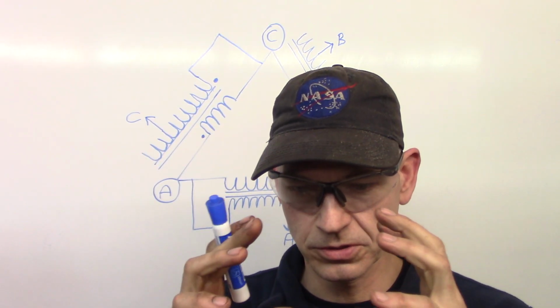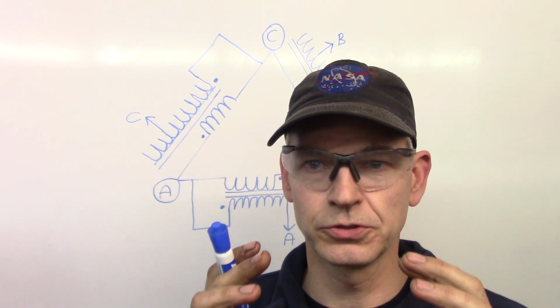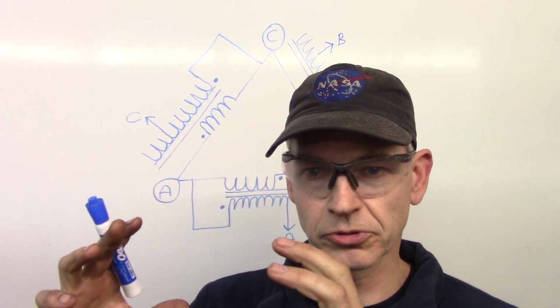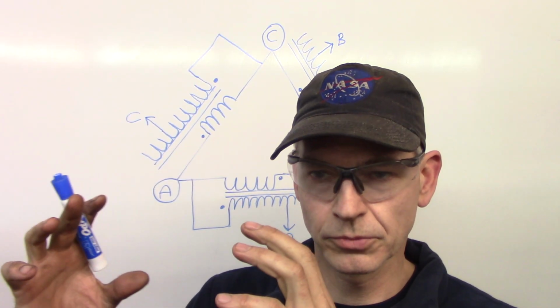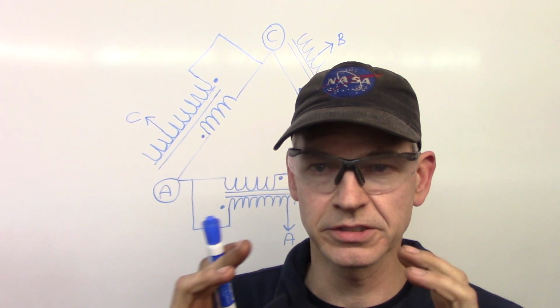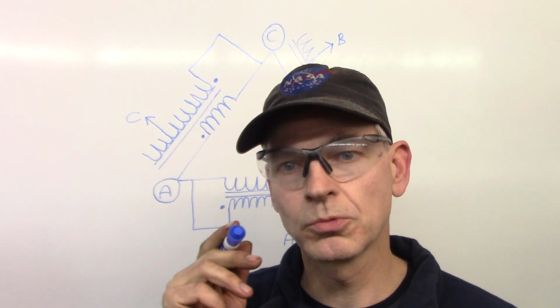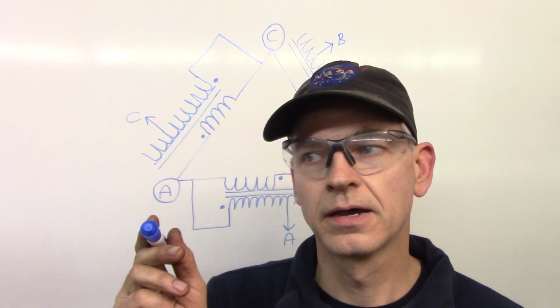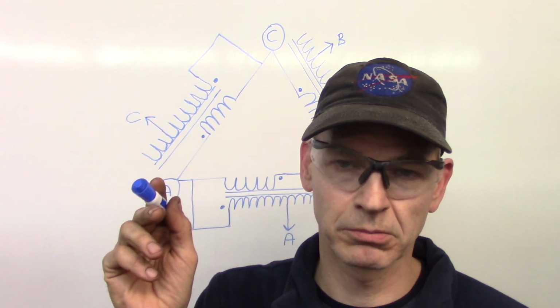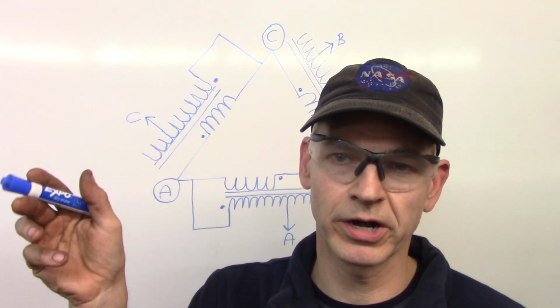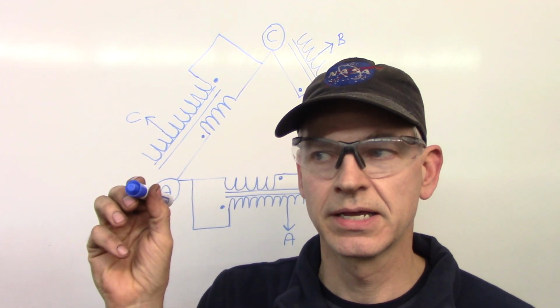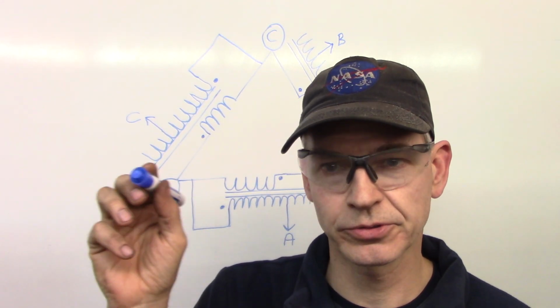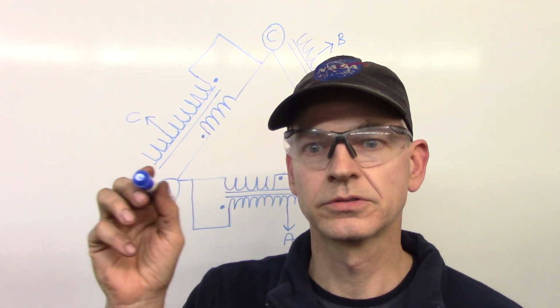So these isolation transformers used in a controls or push button motor controls application are isolation transformers, but I'm going to wire them not as a step-up transformer per se. I'm going to wire them in a step-up configuration, but as an auto transformer. So what does that mean?